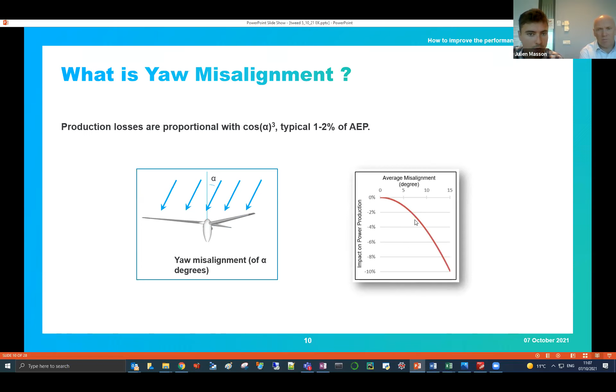So what are the causes of the yaw misalignment? Basically, it's linked with the wind vane. The wind vane is the instrument on top of the nacelle that gives the controller the relative wind direction, so the difference between the wind direction and the nacelle direction. There could be some issue with the wind vane. It could be hardware, linked with an error at installation or during maintenance. But it could be software as well.